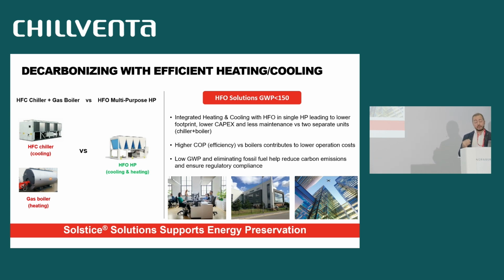So what we see actually on the market is, compared to the legacy heating and cooling systems, where the cooling is provided at a separate chiller and the heating is provided by a separate gas boiler, we see the tendency of multi-purpose heat pumps, which basically provide both heating and cooling, both on the hot water generation and space heating side. And this way, building owners can save on the capex, because instead of two different systems, they only need to take care of one system.